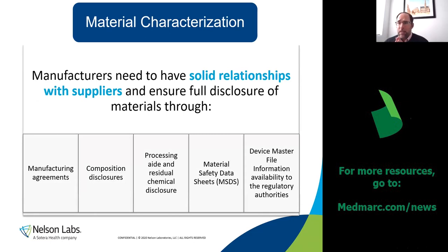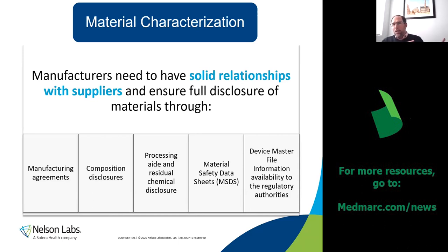When looking at materials, these are things we really push for our clients: when setting up agreements with suppliers, try to get certain things in place first. It's very important to have this information before jumping into any kind of long-term biocompatibility plan. Because if you change the material, or even start to want to use a material for something else and you're trying to do a risk assessment, if you don't have some of this information, it becomes difficult to make any kind of change.